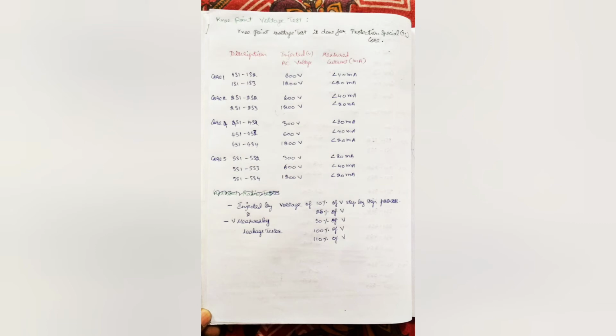So next we are going to the knee point voltage test. Normally the knee point voltage test should be carried out for the protection special core only. So here we have 4 protection special cores. For all the 4 cores, we are going to give the voltage and check the leakage current. In the earlier video I explained how the connections are done for the knee point voltage test, so please refer to that earlier video.